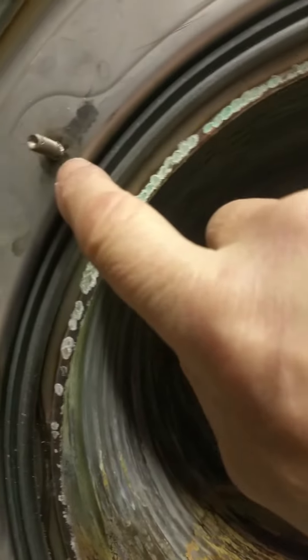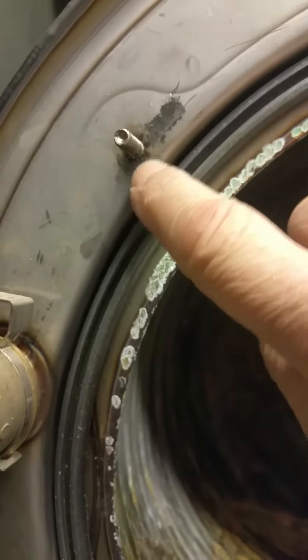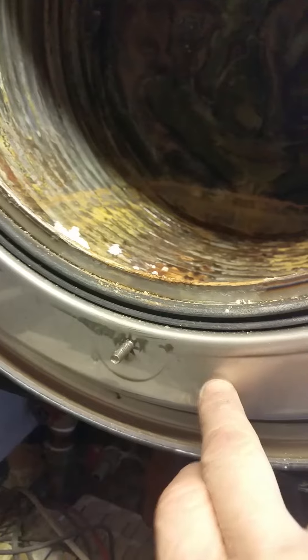This is a highly successful heat exchanger, but the weakness on some of the earlier ones was the points at which the screws were fixed onto the front — on occasion some of them would crack around that screw. That's about the only issue I've had with the Viessmann, other than the 200, which had an aluminium front panel instead of stainless steel.